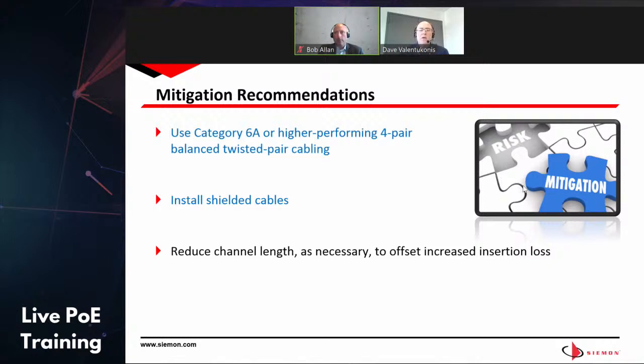It's a twofold approach. You just use the largest conductors you can, which in North America is recognized as category 6A or higher. I guess you could talk about a category 8 cable, but that's really a limited application use. The 7A is something you could use in North America that's a larger gauge, like 23, 22 gauge, and then install shielded cables. And if you don't do any of that, you have to reduce your overall channel length. So if you put those two together, the message behind the message is category 6A shielded cabling is the best you can do for managing remote powering as per North American standards.